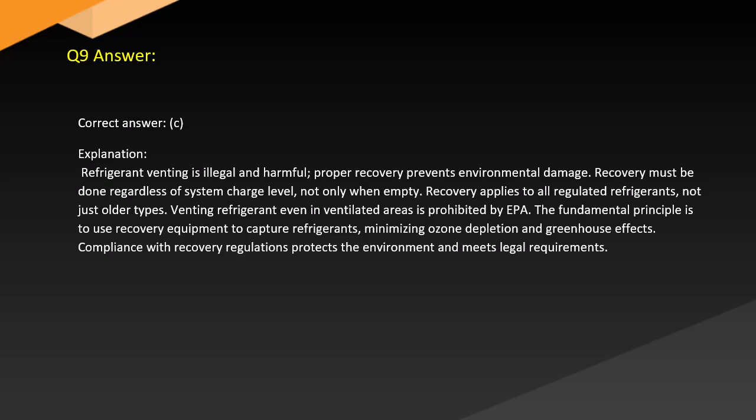Venting refrigerant, even in ventilated areas, is prohibited by the EPA. The fundamental principle is to use recovery equipment to capture refrigerants, preventing ozone depletion and greenhouse effects. Compliance with recovery regulations protects the environment and meets legal requirements.